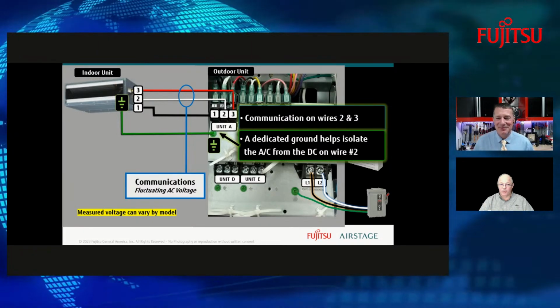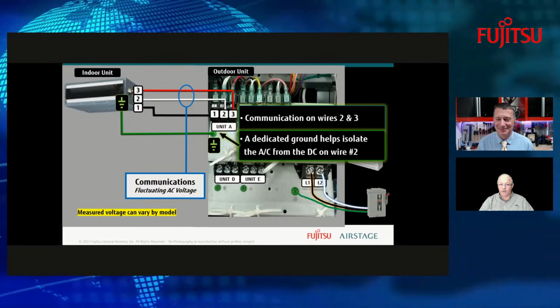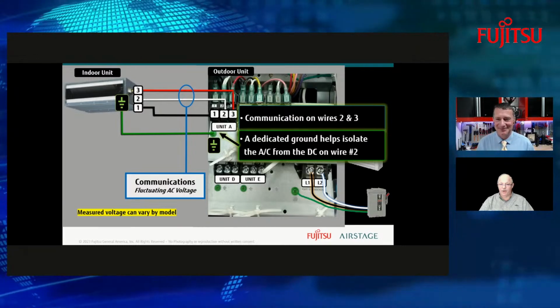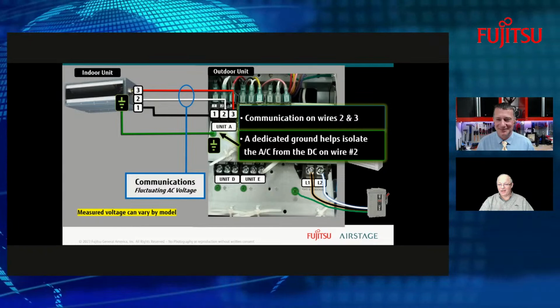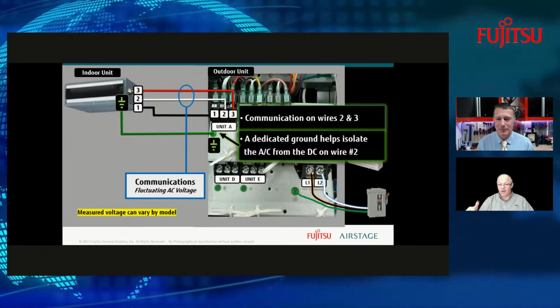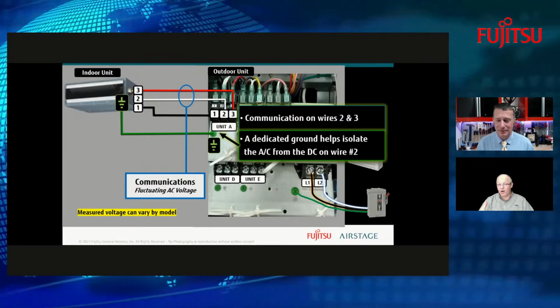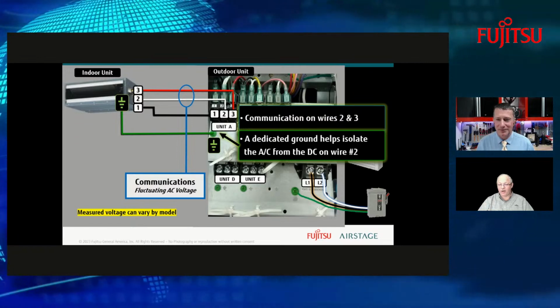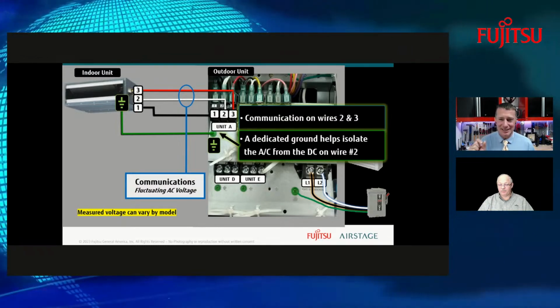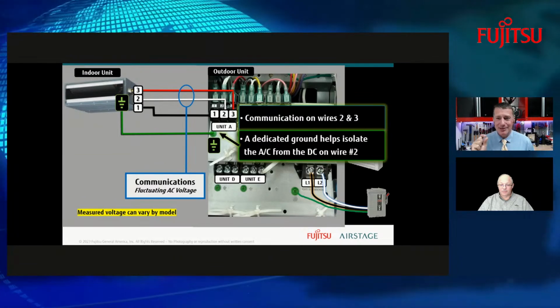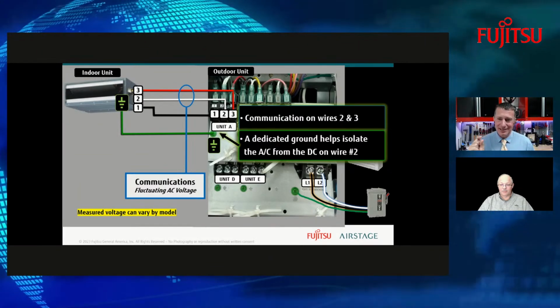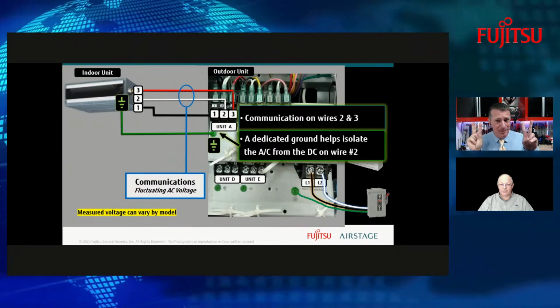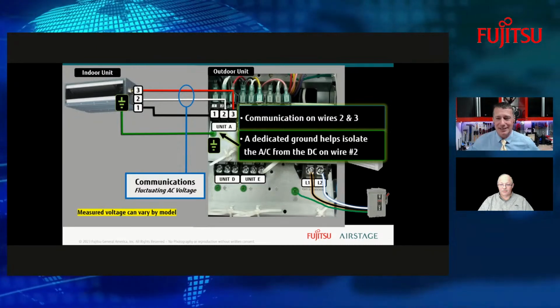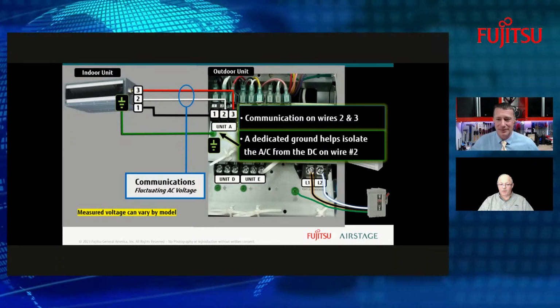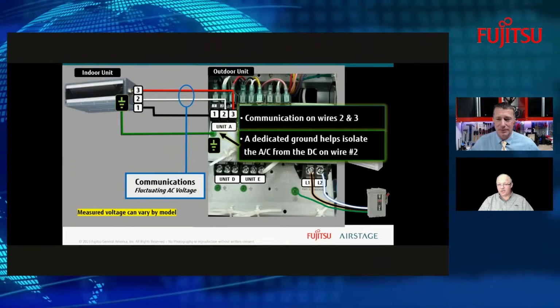Yeah. If it was only 3, well, don't you have a dedicated green ground wire? No. The first thing they would have to do is make sure they've got that, because we're trying to isolate the AC from the DC on wire number 2 by having that dedicated ground. A lot of people don't understand what is happening there on that number 2 wire. That is a shared, somewhat common wire between our AC and our DC voltages. Yeah, a lot of people don't understand how they both can exist on the same wire.